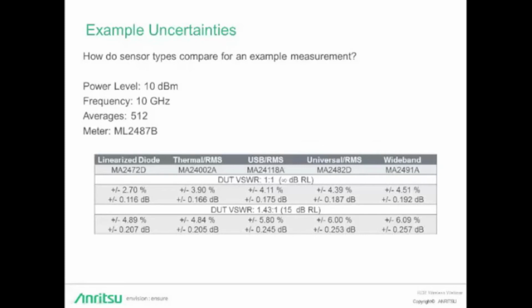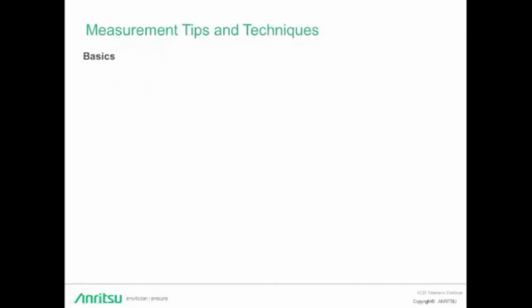However, we can see that the diode-based sensors are much more sensitive to match with the DUT than the thermal sensors. The USB sensor and universal RMS sensors are very similar. The USB is a little better because the universal sensor has some added uncertainty associated with the reference calibration. Wideband sensor has the most uncertainty because its added sensitivity makes it more difficult to linearize, increasing the linearity contribution to its uncertainty. So let's discuss some basic tips.